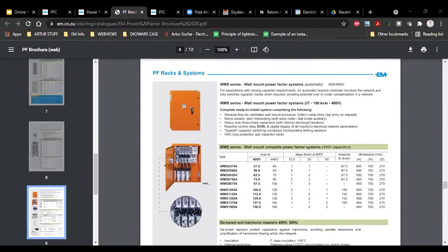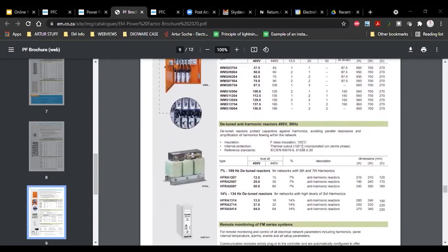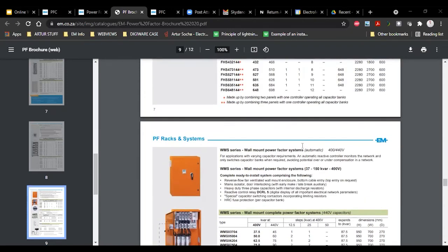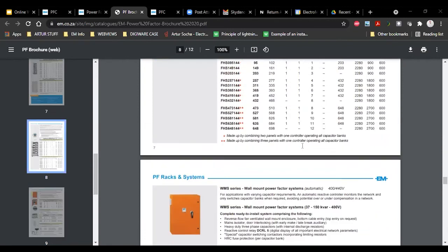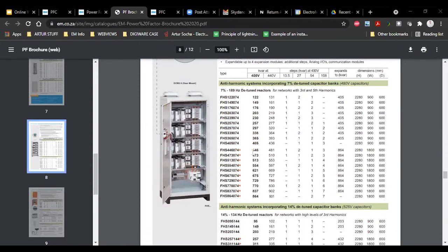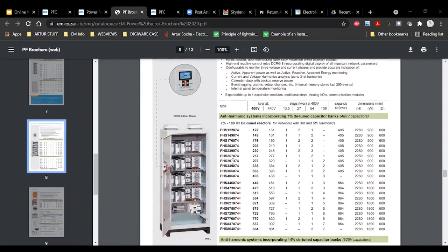And then we do a small series of wall mount systems where you may have a small farm somewhere. The guy's got some basic issues, doesn't have any drives on his farm, and he says, can you help me out? I've got bad PF. The council is hitting me on the power factor side. There are these sorts of solutions. Note that these solutions are for indoor applications. We have been requested for outdoor applications. It's a little bit complex because of the amount of heating that can happen internally. It means these systems vent quite a lot of air.